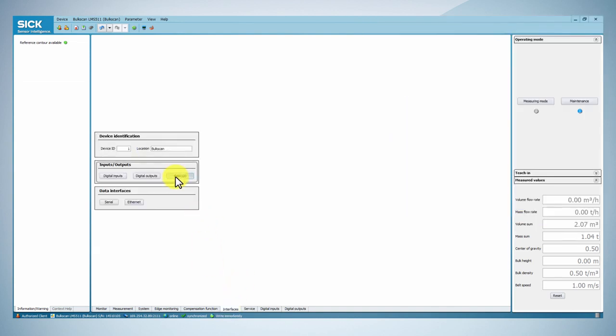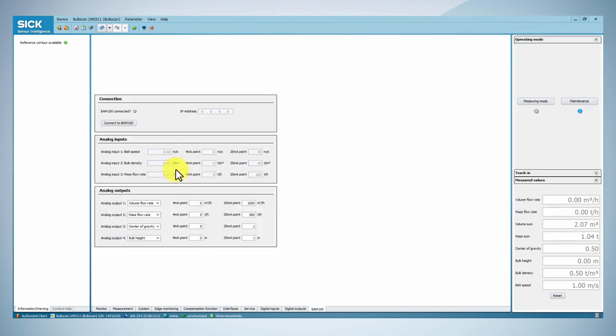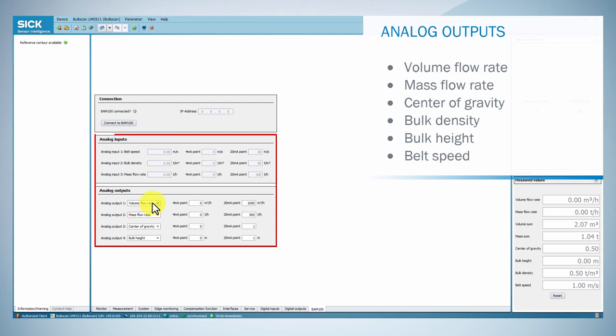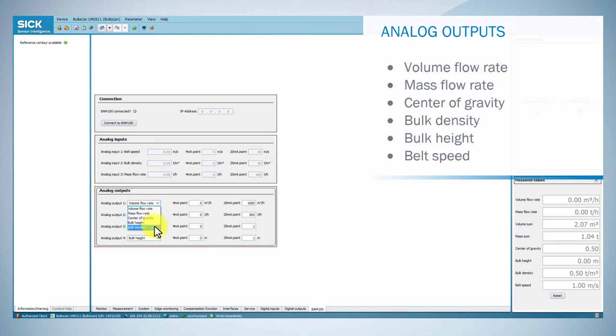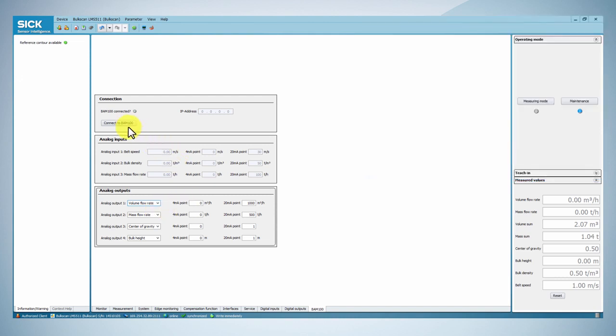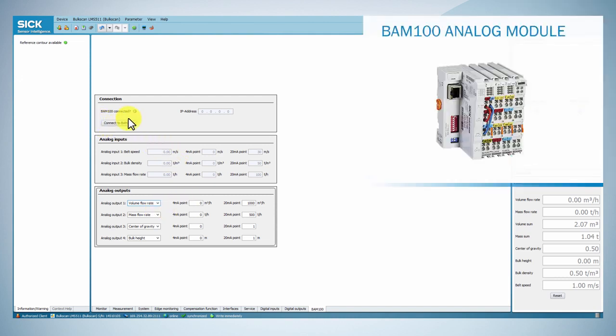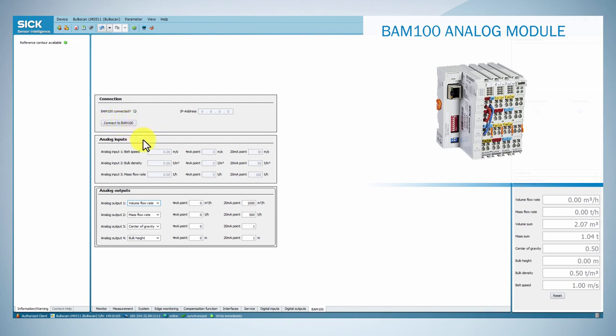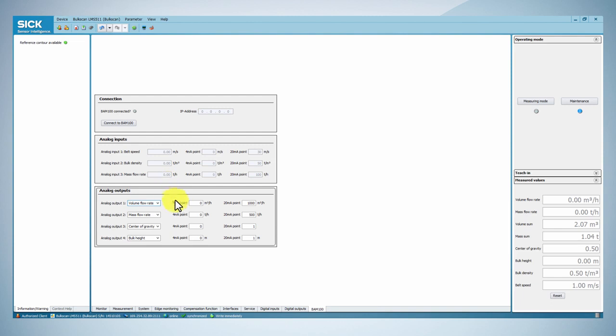The Bulkscan can read inputs and outputs analog for 4-20 milliamp values via the analog module BAM100. To configure the module BAM100, go to the Interface tab and in the Inputs Outputs box click the BAM100 button. Then, you can configure the analog inputs and outputs.